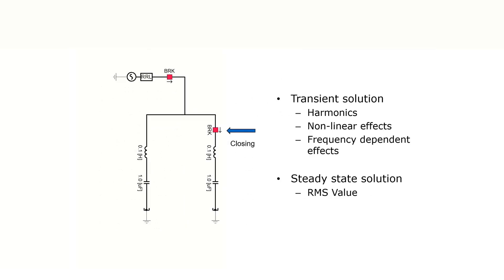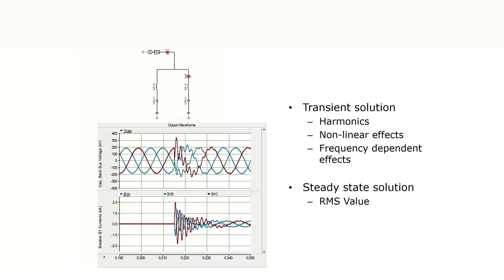PSCAD is a software people heavily use for transient studies. Let me show a simple example — this is a simple capacitor bank energizing simulation. It's a very simple circuit. You see the capacitor bank here and we have what you call an inrush limiting reactor. Normally the capacitor is equipped with this kind of reactor to limit the inrush current, and you have the breaker here and a source representing the power system.